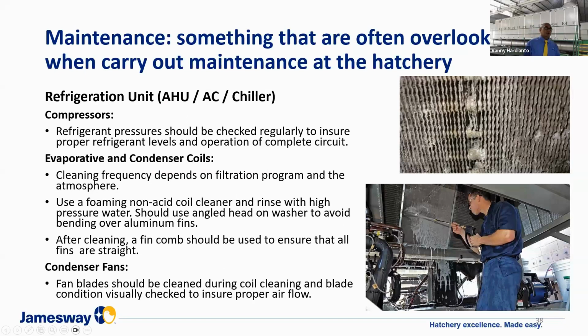With the refrigerated air handling unit or the air conditioner, or maybe also the chiller, we have to check the refrigerant pressure regularly. Lack of refrigerant pressure will cause a lack of cooling power for the unit. The evaporator and the condenser coil also need to be checked regularly to ensure the coil is always clean. It's quite similar to the fin coil in the air handling unit. But you need to be careful with the aluminum fin coil that may be damaged during maintenance.